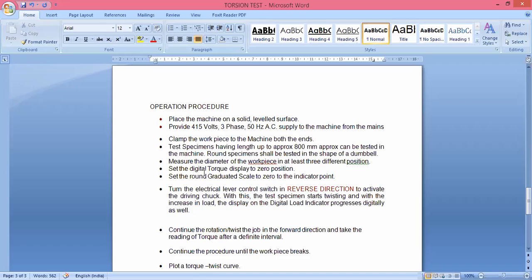Set the digital torque display to zero position. After setting and fixing the twist, we have to set the digital display device to zero position by pressing the zero switch. Next, we have to push the peak switch P, which will give you the peak load when it reaches the peak in the graduated scale in the display device. Set the round graduated scale to zero.